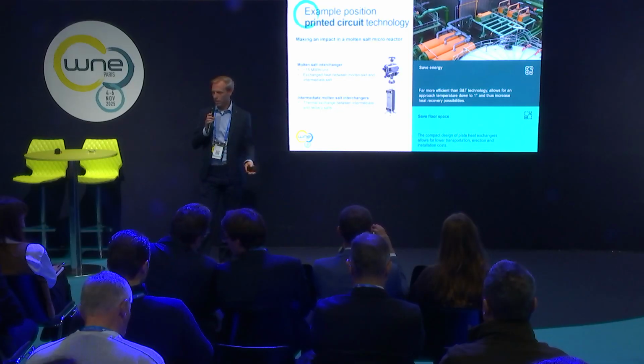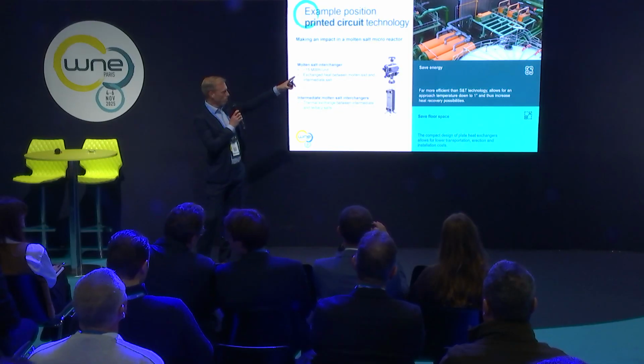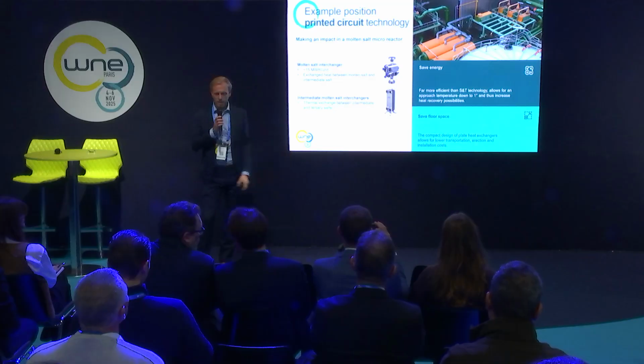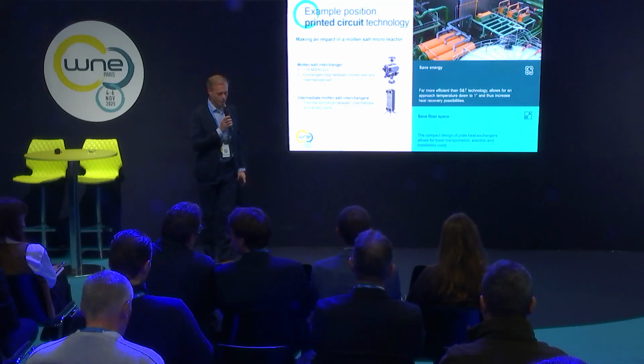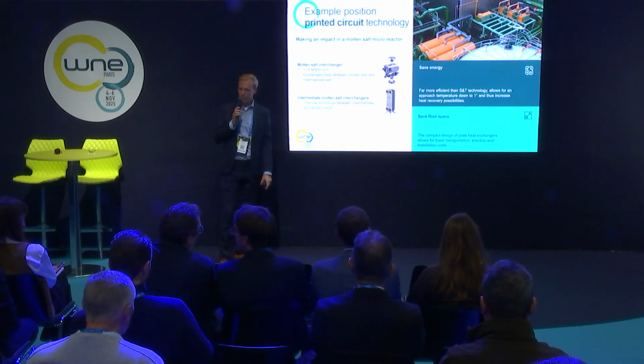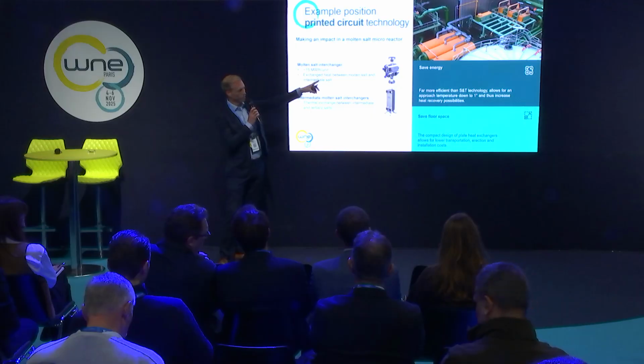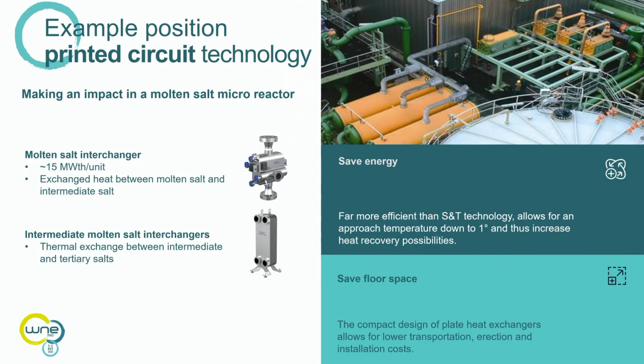And if you want to see the real power of plate technology, take a look at the corner. This is an example of plate type heat exchangers. You can see in the right top corner those 3 boxes. Those have the same capacity as 6 of the shell and tube type heat exchangers shown in the left corner, so you can see the size difference.